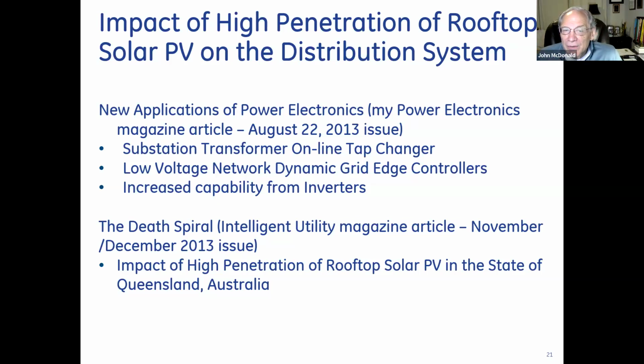The challenge is the tap changer in the substation is a mechanical controller, and its job is to keep the secondary voltage constant as the primary voltage fluctuates. When you have a high penetration of PV panels, the volatility of the voltage increases, and the tap changer works much more frequently because of that volatility. Its lifetime, in this particular case, went from 35 years to less than 2 years.